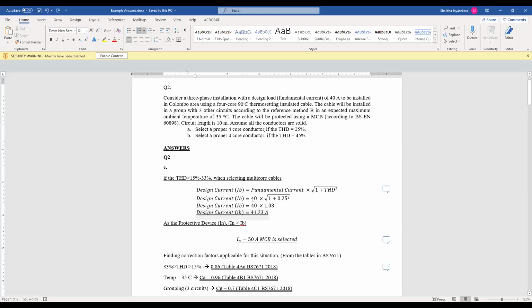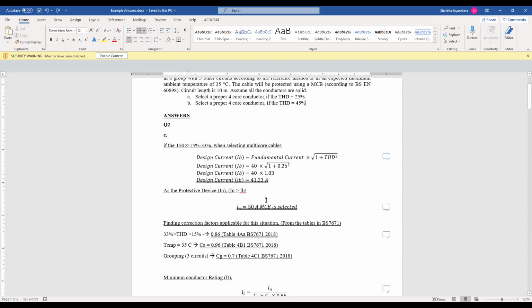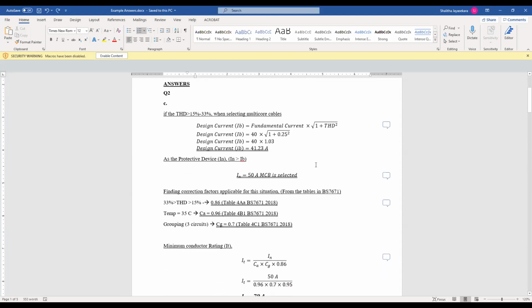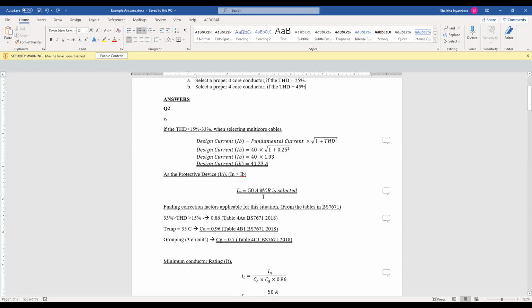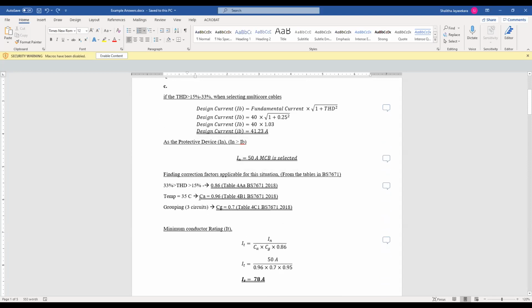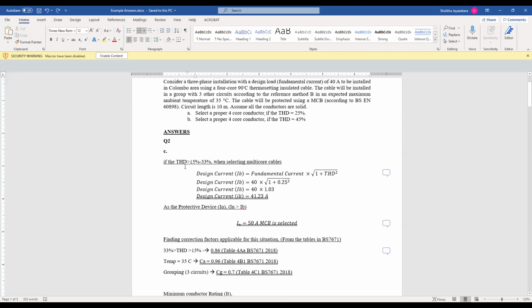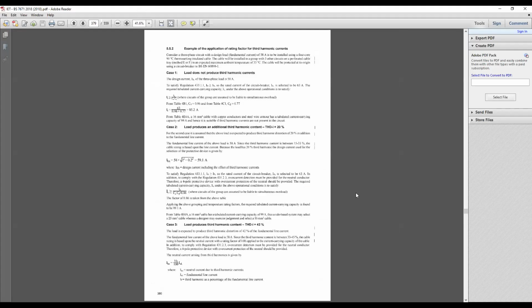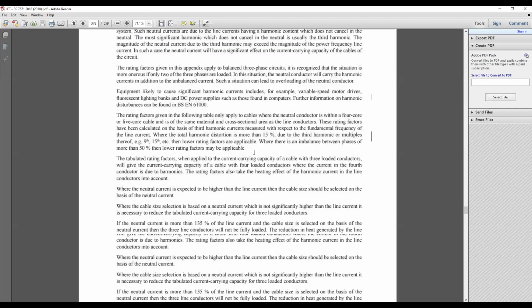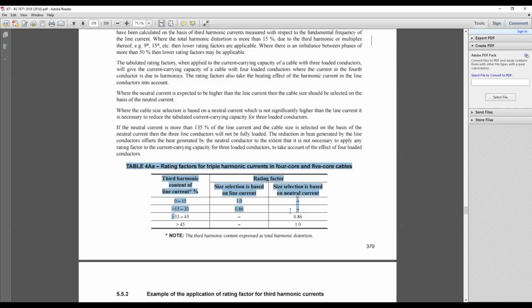After calculating the design current, you get this value, and now the whole process is equal to the earlier designs we conducted. So you know how to apply rating factors. Here is one special thing: our design has 25% THD, but when it comes to designs with third harmonics, you have to consider another rating factor. This is called the third harmonic rating factor. This is also mentioned in BS 7671. I think you should remember these page numbers. This is page 379.